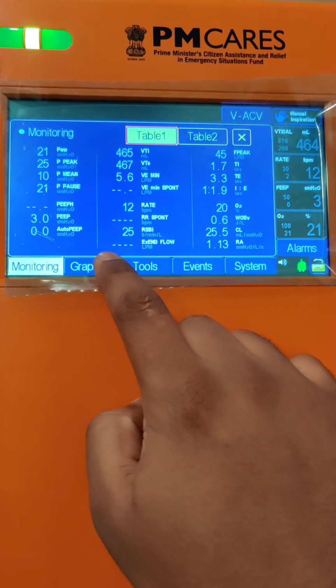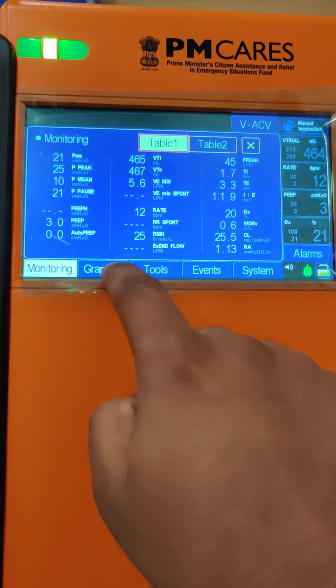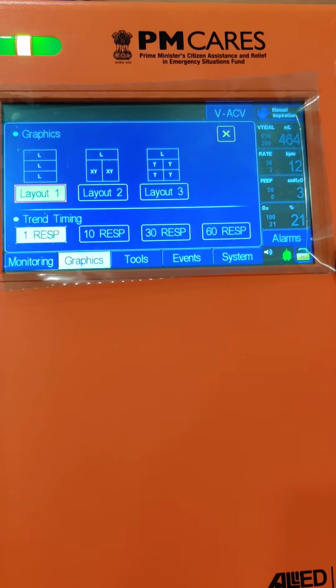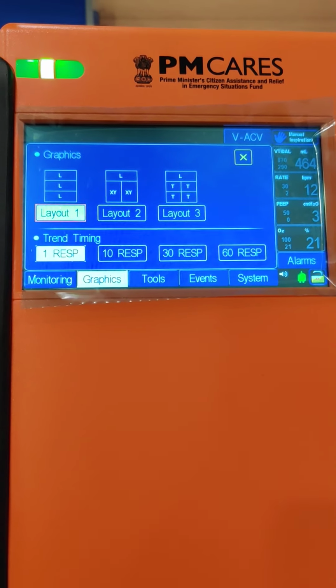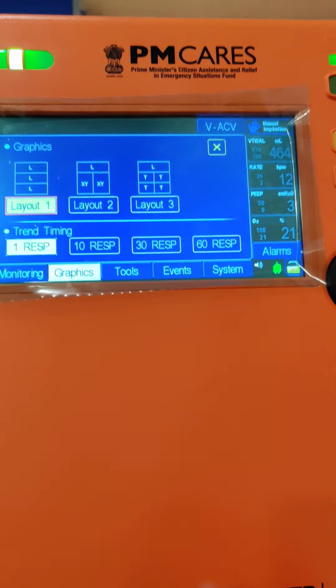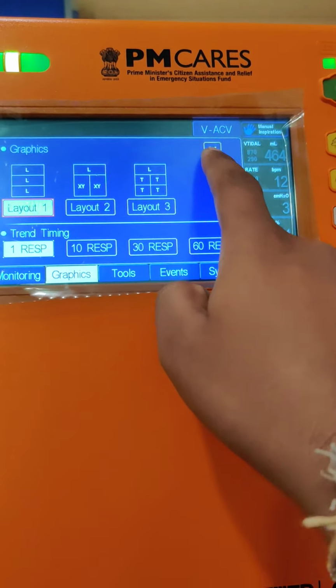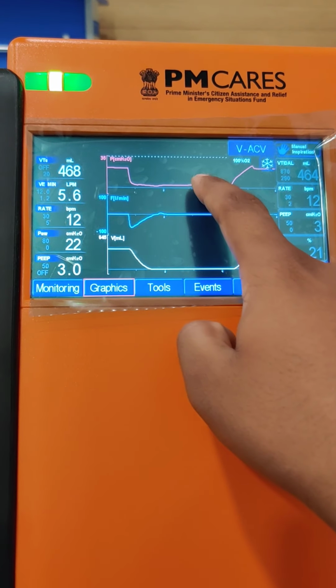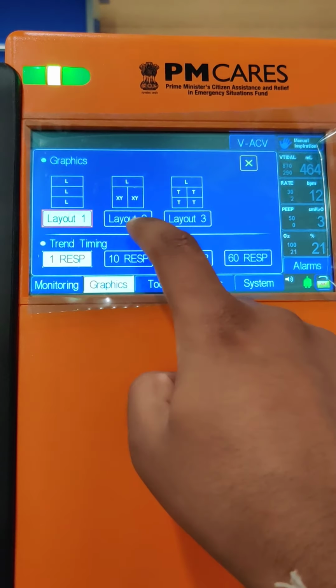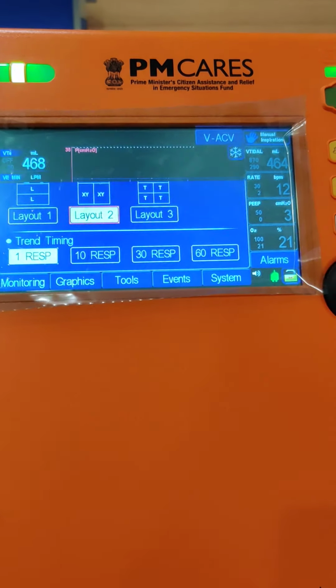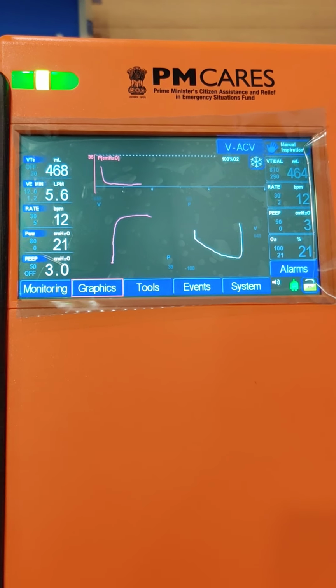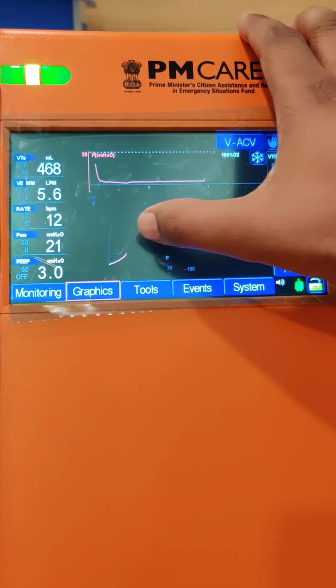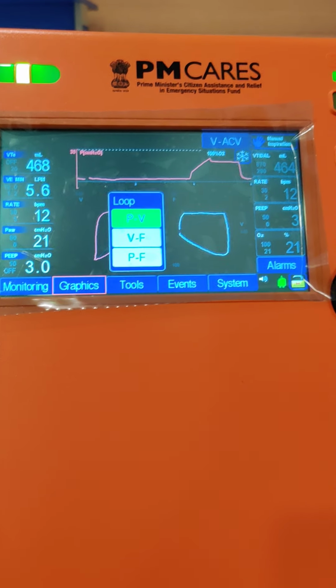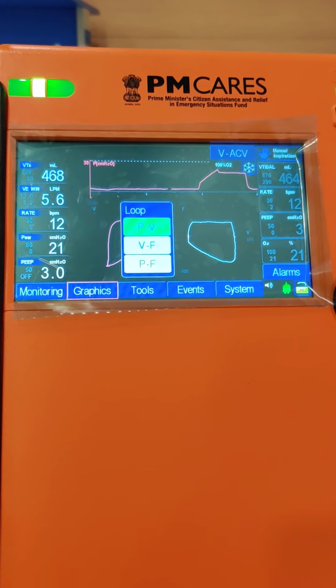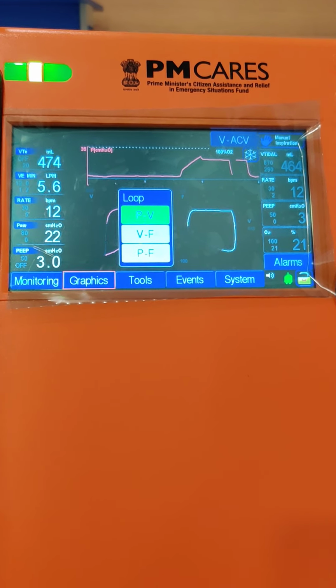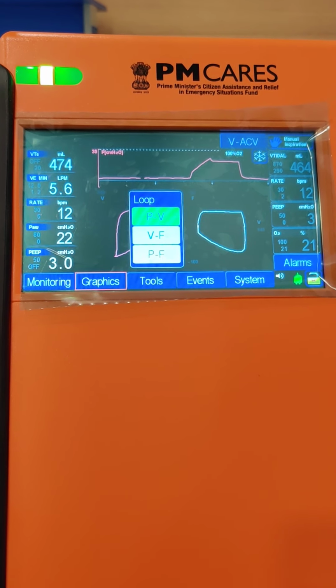Now coming on to the next shortcut key, that is the graphics. Here you can see there are three types of layout given on the display. Layout 1 shows the three waveforms: the pressure, the flow and the volume. If you go into layout 2, then with one waveform you will get two loops. You can change between three loops, but two loops are displayed simultaneously on the screen. You can select between pressure-volume, volume-flow and pressure-flow loops.